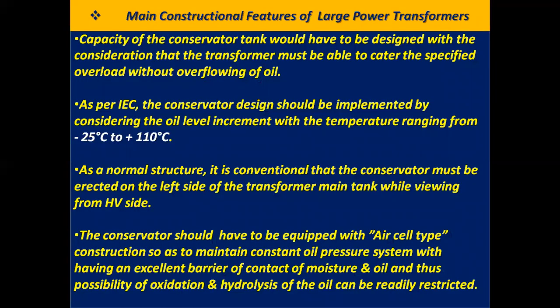Let's start with main constructional features of large power transformers. Capacity of the conservator tank would have to be designed with the consideration that the transformer must be able to cater the specified overload without overflowing of oil. As per IEC, the conservator design should be implemented by considering the oil level increment with the temperature ranging from minus 25 degrees centigrade to plus 110 degrees centigrade. As a normal structure, it is conventional that the conservator must be erected on the left side of the transformer main tank while viewing from HV side.